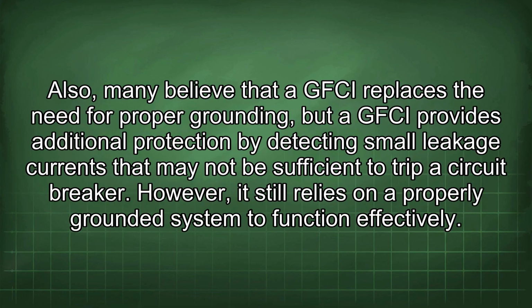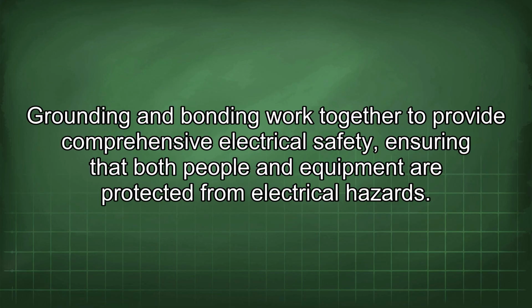Also, many believe that a GFCI replaces the need for proper grounding, but a GFCI provides additional protection by detecting small leakage currents that may not be sufficient to trip a circuit breaker. However, it still relies on a properly grounded system to function effectively. Grounding and bonding work together to provide comprehensive electrical safety, ensuring that both people and equipment are protected from electrical hazards.